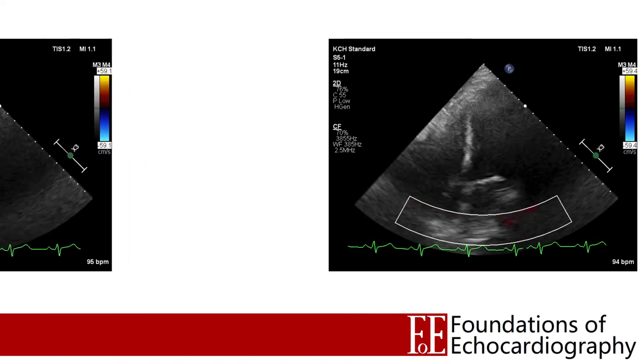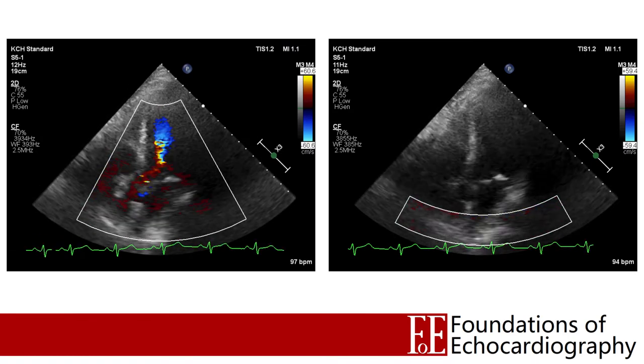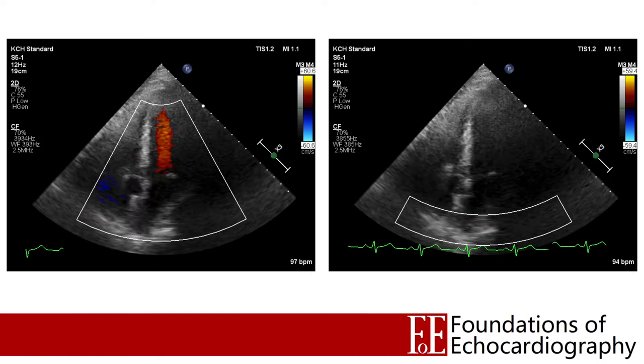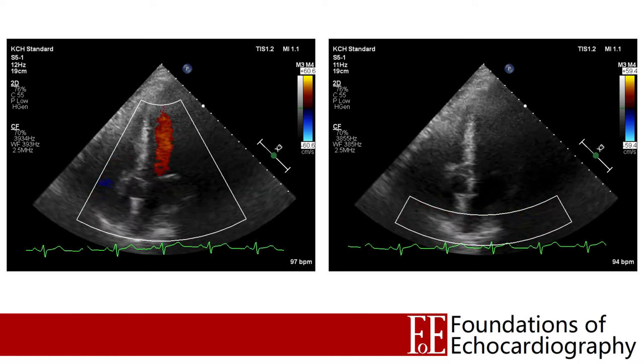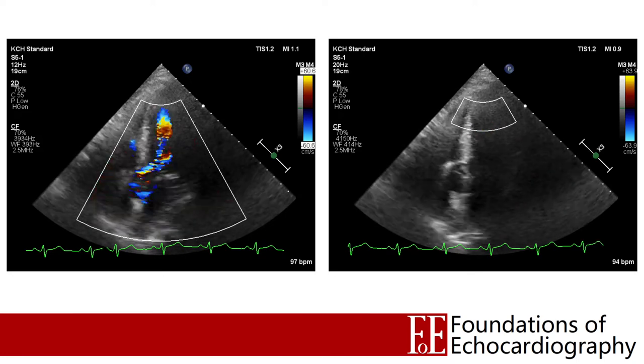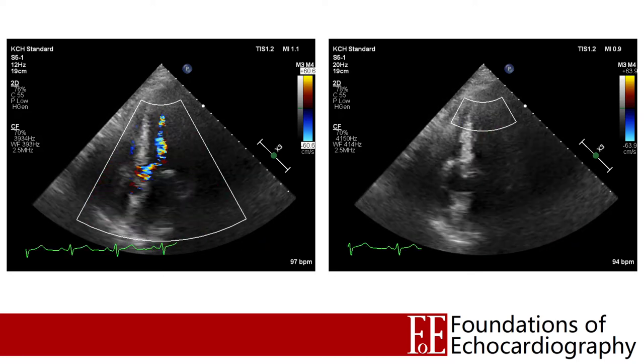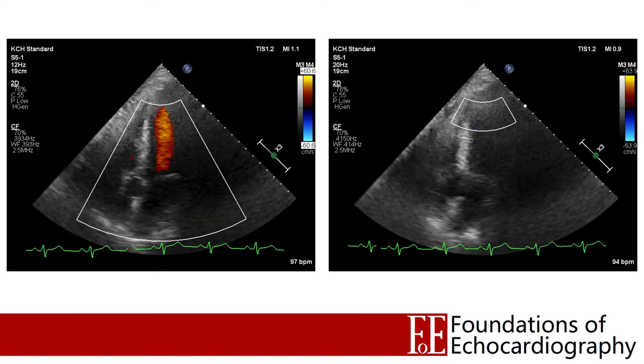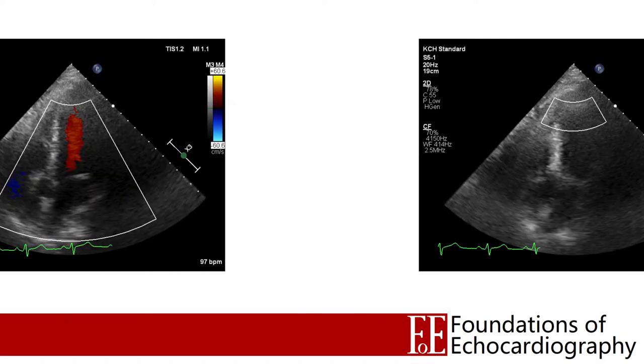What would happen to our frame rate if we used a colour box with a similar width to that on the right but displaying colour information from all that near-field area as well? The frame rate is essentially identical. But if we adjust our colour box to maintain the same width while only asking for information from the near field, the frame rate increases from 12 frames per second up to 20 frames per second. The guiding principle is the same as for generating a 2D image: keep your box as small as possible while still covering the entire region of interest.